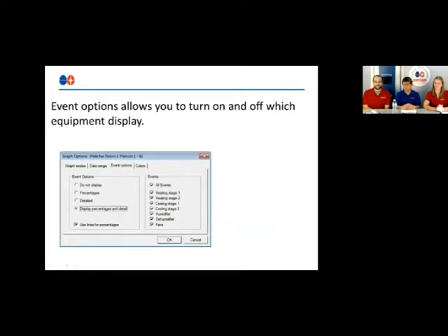You can also adjust whether you want detailed information of, in this example, what the ventilation is doing. You can display it as whether something is on or off, or as a percentage of how often it has been on in the last 5 minutes. So if you're trying to diagnose temperature, you can turn off the events for humidifiers, dehumidifiers, and fans, and that will zoom in on that data so you can more closely identify the times related to the temperature or whatever issue.